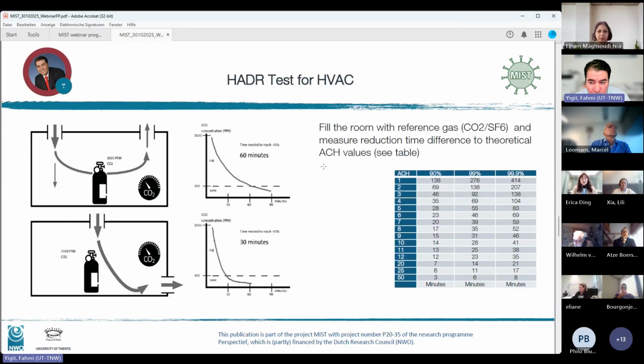Why? Look at a test we developed in the study I will present. Theoretically you have a space, you fill it with CO2, then you press the button of the HVAC system and wait. How long will it take until it is reduced 90%? If you look at the theoretical values on the table on the right, you have 23 minutes to reduce 90% at an air change rate of 6.